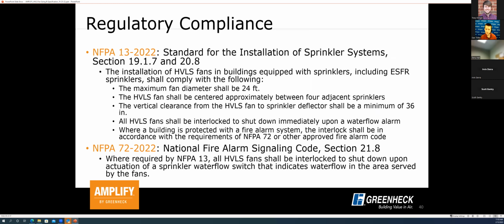I referenced regulatory compliance a few times throughout the talk today, but this is another very critical factor in the design process. We have to make sure that the selected fans and the layout of those fans in the building comply with codes and standards available in the industry. The two probably most critical are NFPA standards that are adopted into fire code. These are NFPA 13 and NFPA 72. I put all of the direct text from the standards on screen here for reference, but I'll summarize them at a very high level. What these standards require is that the HVLS fan itself is sized and located so that it does not impact the flow of a sprinkler system in the event of a fire in a building, and that it does not impact the spread of fire in that fire event as well.